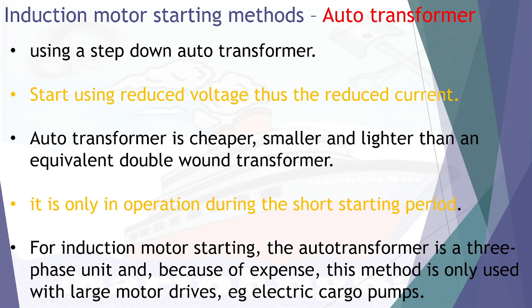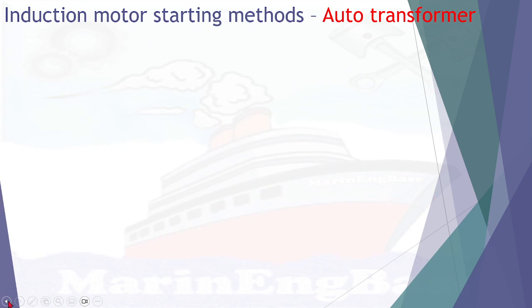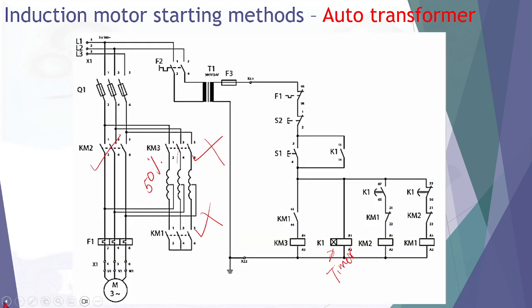One important caution: the timer relay is critical in this circuit. If the timer relay fails, the motor may continue running on the auto transformer indefinitely and eventually the transformer will burn out.